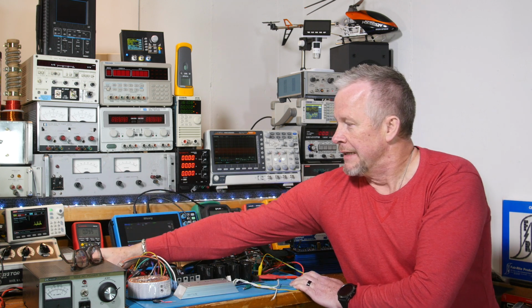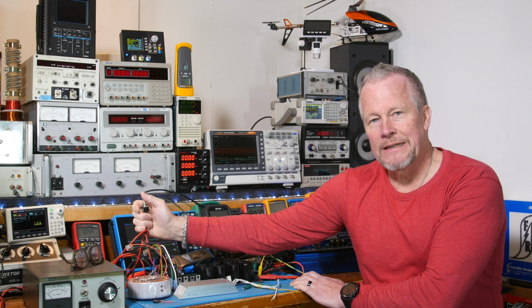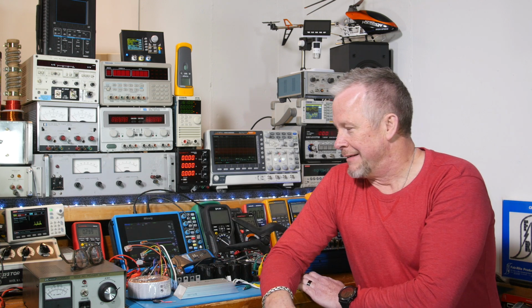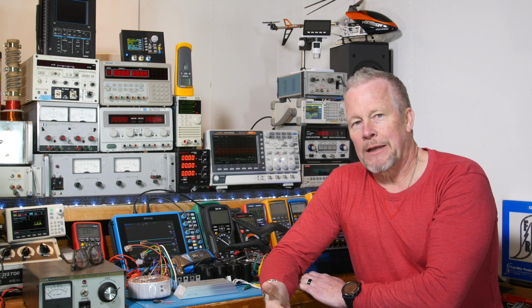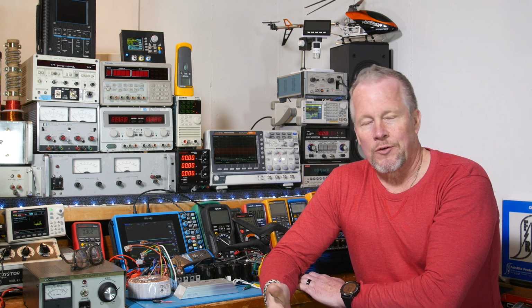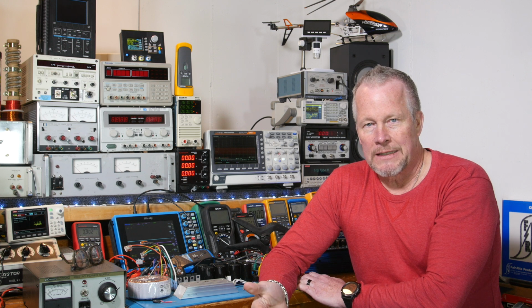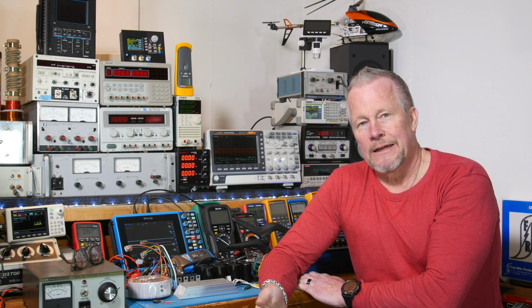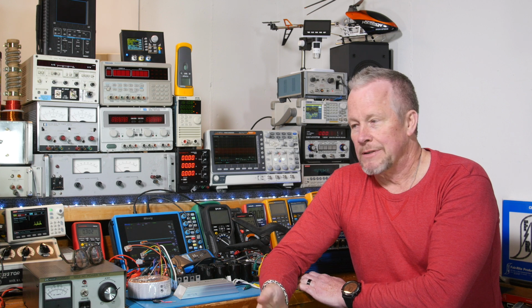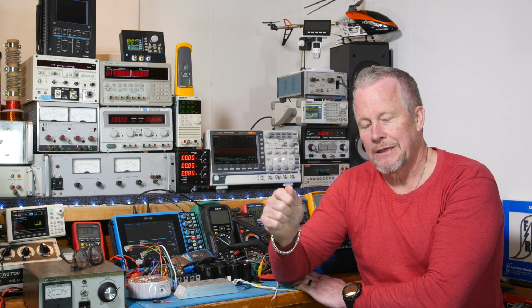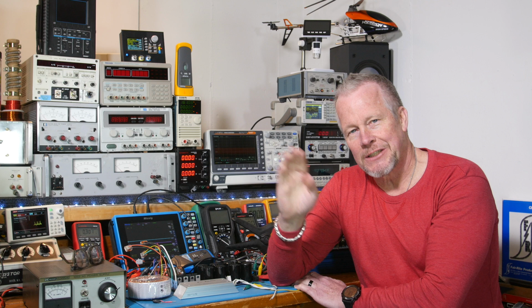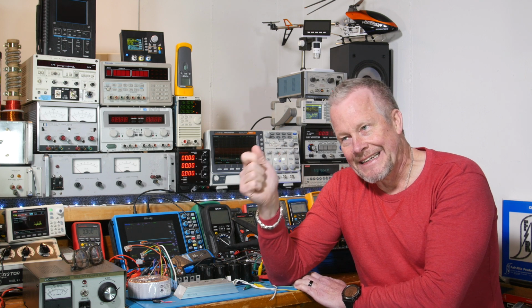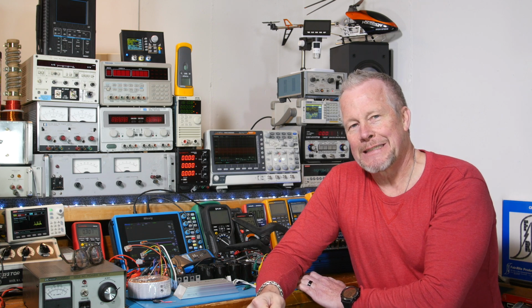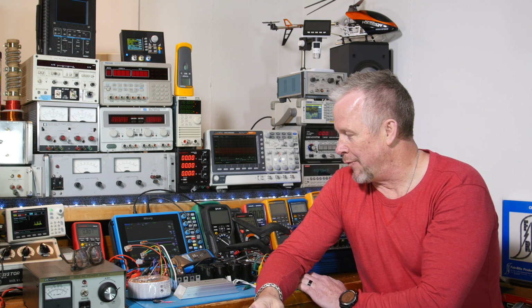When you're just haphazardly flipping the switch on and off, hoping by luck you'll get the right waveform - that's not a bad way to do it, but you're going to have to try it maybe 5 times at least, 10 at least, maybe up to 20 times or more. As you do it, you might notice you're catching the same time every time, and you're just thinking, come on, get a better peak this time. So you just have to do it a bunch of times to try to get the peak waveform.